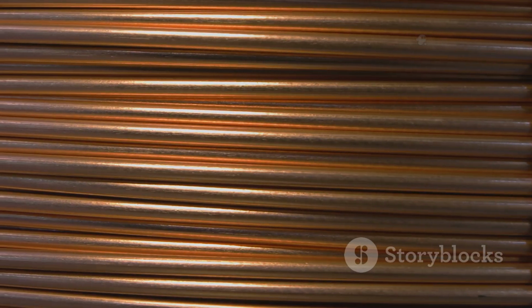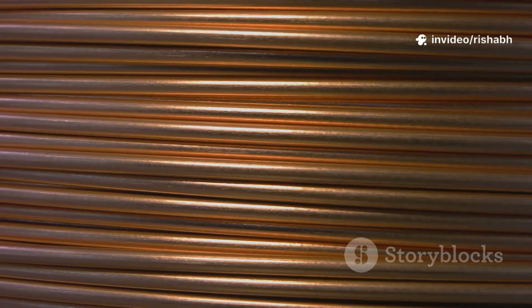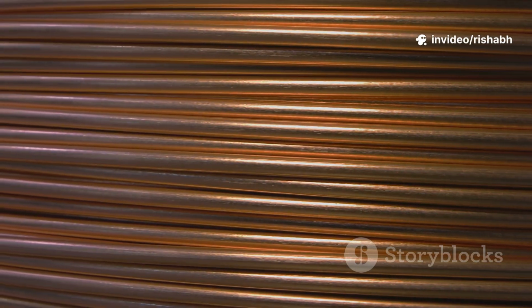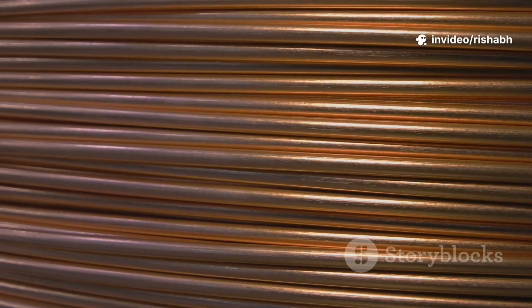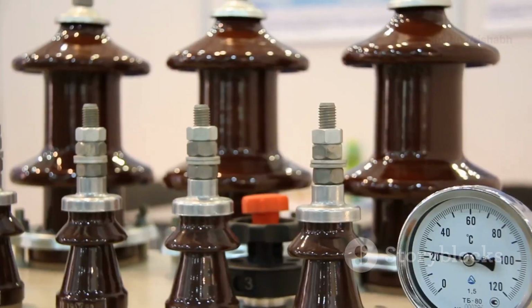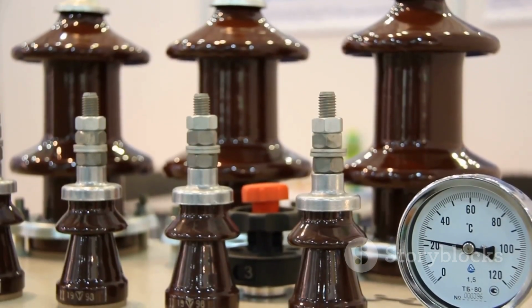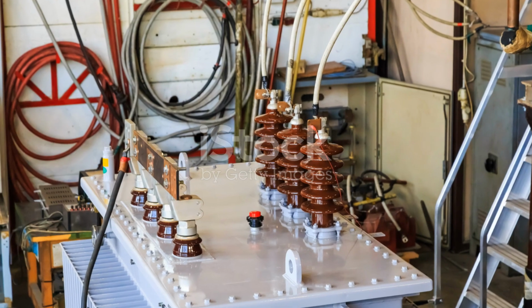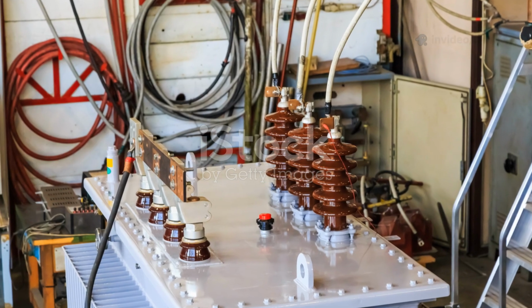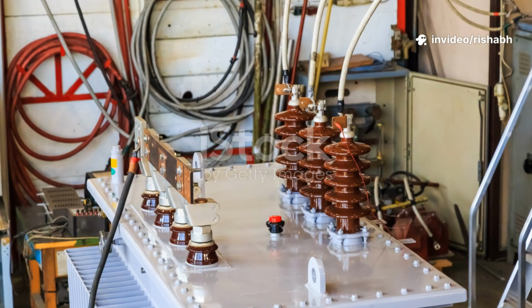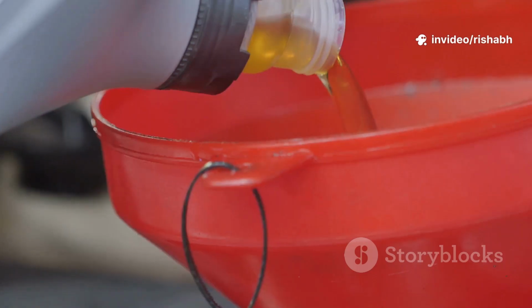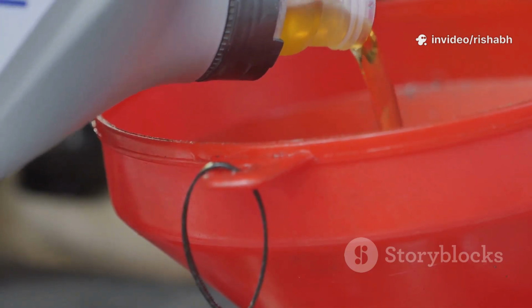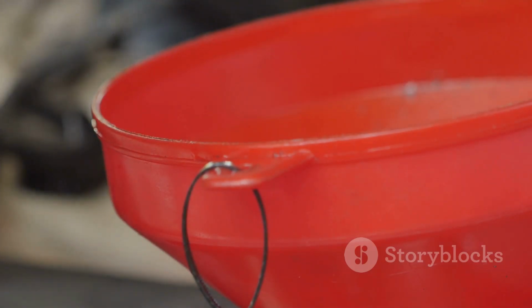The solids, as we've seen, are the cellulose-based kraft paper and pressboard that wrap the conductors and form barriers. But these materials alone are just not enough. Their true power is unlocked when they are completely impregnated with a special liquid, transformer oil. This oil is, you could say, the lifeblood of the transformer.